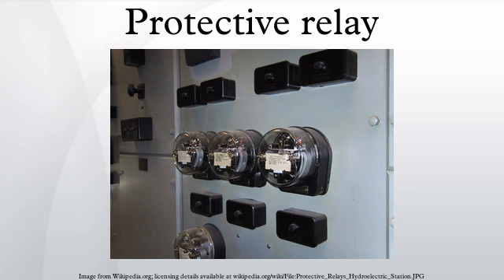Static relays with no or few moving parts became practical with the introduction of the transistor. Static relays offer the advantage of higher sensitivity than purely electromechanical relays, because power to operate output contacts is derived from a separate supply, not from the signal circuits. Static relays eliminated or reduced contact bounce, and could provide fast operation, long life and low maintenance.